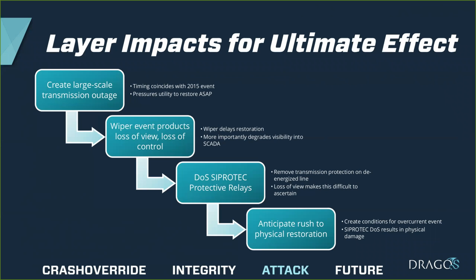Then we layer on the denial of service against the SIPROTEC protective relays. At first this seems nonsensical, because we have de-energized lines—what's the point of removing protection for something that's not carrying any power? However, what happens is that you've removed protection not for the line in the state it's currently in, but knowing operators are rushing to reconnect these lines while lacking good visibility into their environment. You now put operators in a position where they'll reconnect an unprotected line in the rush to restore operations, which creates the conditions for a potentially hazardous physical event, such as an overcurrent event at the time of immediate impact, or other delayed physical impacts before the protective relays can be reconfigured and brought back online.